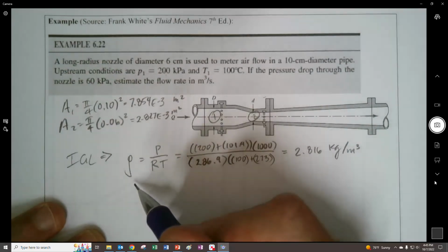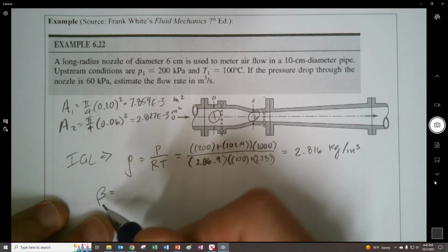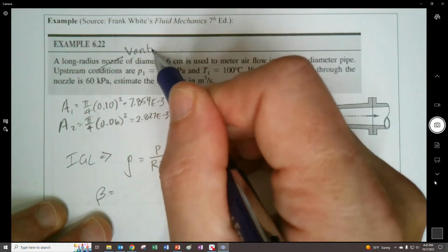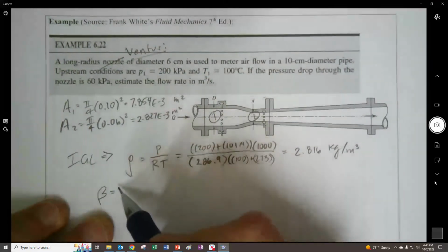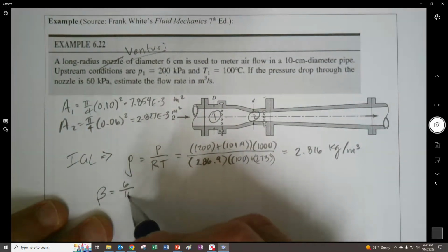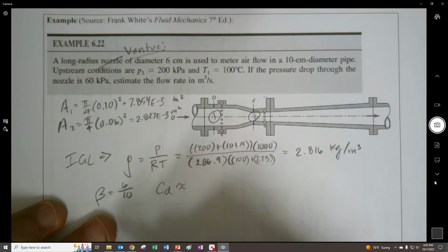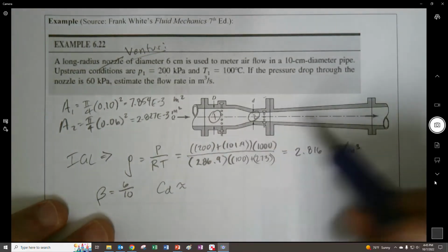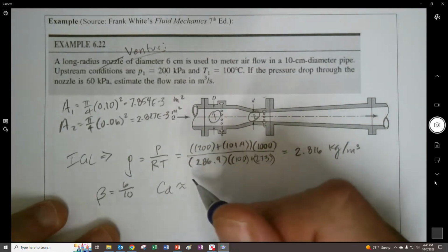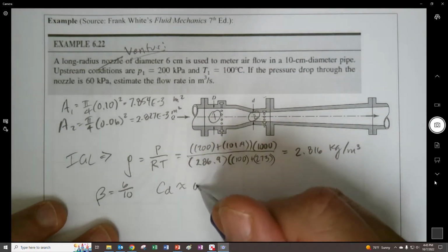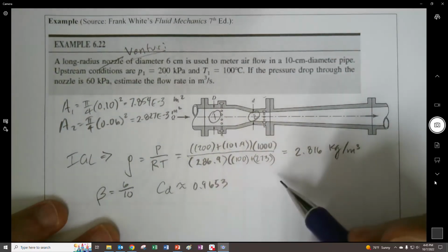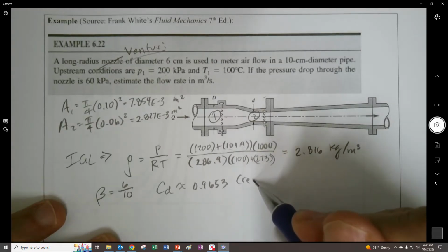I went ahead and used a curve for a Venturi. I'm sure that my numbers came out differently than theirs. But I used a curve that was supplied that gives the discharge coefficient, this one right here, based on beta. We know that it's going to be a function of other things like velocity. Usually Reynolds number is what we use. But this one, I went ahead and used this number. These are the numbers that I have. But we have to be certain that we get the thing from the right source. So don't be like me, kids. We might want to recheck this at some time.